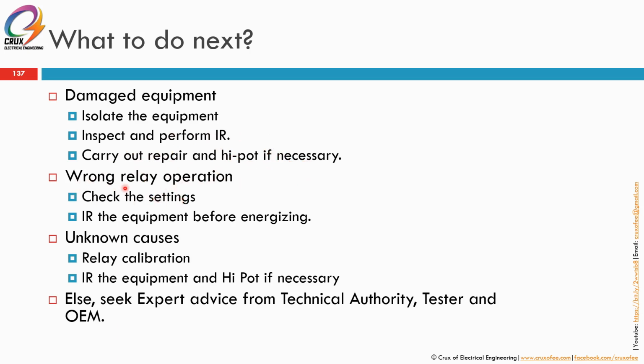Okay, if it's a wrong relay operation, meaning the relay tripped but there is no damaged equipment, the relay tripped on its own. Check the settings, check whether there was any batch defect around the world, check electrical forums, all that. And then IR the equipment before energizing. Normally a wrong relay operation is due to the setting, or the relay is faulty itself. For unknown causes, relay calibration: you left it, the relay tester left it in the testing setting, which is maybe lower than the actual setting. Then you have to IR the equipment and high pot if necessary.